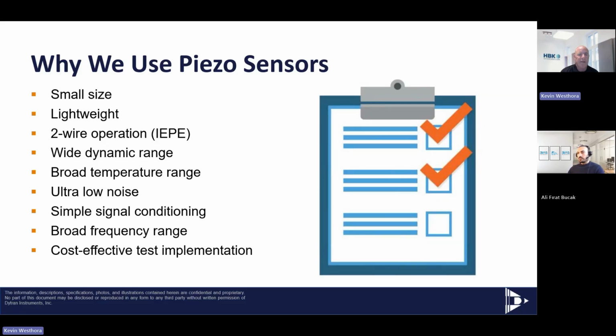And then lastly, we have broad frequency range. So we make sensors, like I mentioned, for seismic applications that go down to fractions of a hertz, 0.1, 0.05 hertz. And then we have sensors that go all the way up to 20 kilohertz. So a very broad frequency range. That's not the case with the DC MEMS accelerometers. They go from 0 hertz, hence the word DC frequency, to roughly about 1 or 2 kilohertz maximum. So they're very limited in the upper frequency. But piezoelectric sensors typically can easily go to 10 kilohertz.